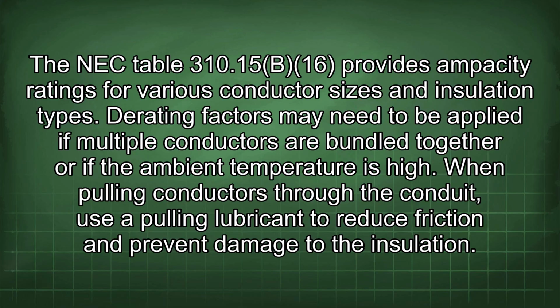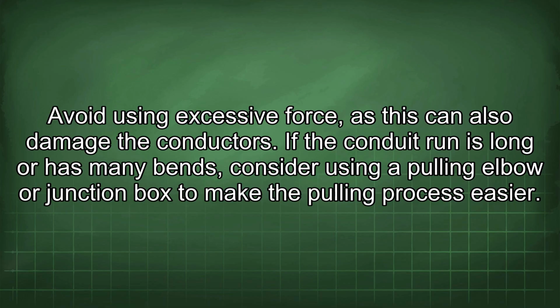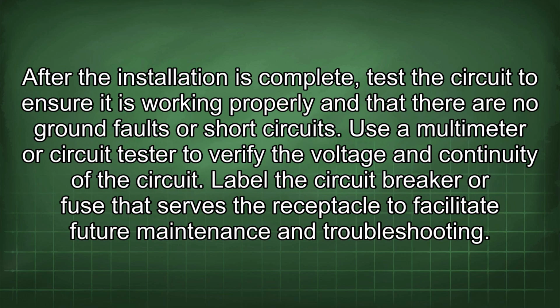When pulling conductors through the conduit, use a pulling lubricant to reduce friction and prevent damage to the insulation. Avoid using excessive force, as this can also damage the conductors. If the conduit run is long or has many bends, consider using a pulling elbow or junction box to make the pulling process easier. After the installation is complete, test the circuit to ensure it is working properly and that there are no ground faults or short circuits. Use a multimeter or circuit tester to verify the voltage and continuity of the circuit. Label the circuit breaker or fuse that serves the receptacle to facilitate future maintenance and troubleshooting.